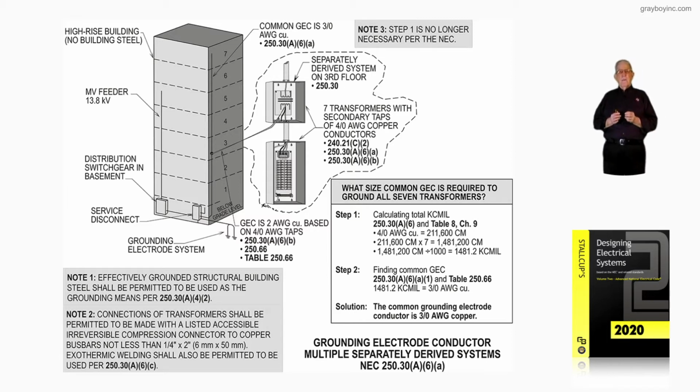250.30(A)(6)(c), as in car. Now, if my memory serves me correctly, if we looked at the Emerald book of IEEE, after about 250 kcmil being routed, as you see in the illustration, from floor to floor, connected into the grounding electrode system, this is what we call a common grounding electrode conductor per code. Read all about it in 250.68 and 250.64 of the code.